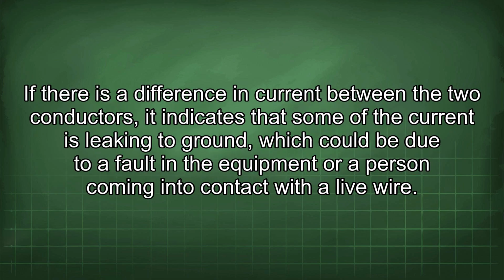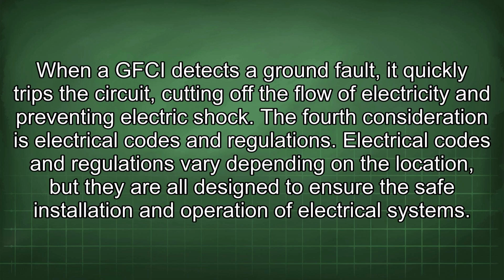If there is a difference in current between the two conductors, it indicates that some of the current is leaking to ground, which could be due to a fault in the equipment or a person coming into contact with a live wire. When a GFCI detects a ground fault, it quickly trips the circuit, cutting off the flow of electricity and preventing electric shock. The fourth consideration is electrical codes and regulations.